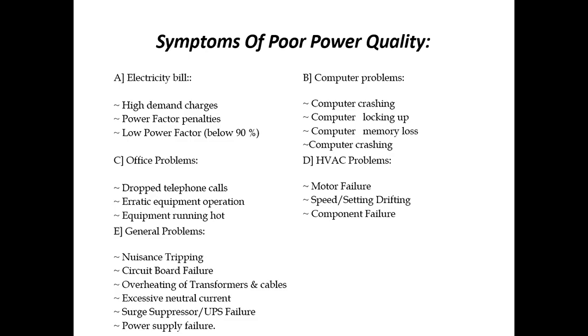Then the next point that we are going to discuss is the general problems, such as noise and tripping. If the power quality is poor, you will get some noise. Then circuit breaker failure or circuit board failure, many times. Overheating of the transformer and overheating of the cable: if harmonics are present in the system, or in the input given to the transformer, you will get overheating of the transformer and cables. Excessive neutral current, surge suppressor failure, UPS failure, power supply failure. So these are all symptoms of power quality issues. If the power quality provided by the sources is not as per the requirements and standards, then definitely you will get all these problems in your equipment at your utility system. So these are the symptoms of poor power quality.